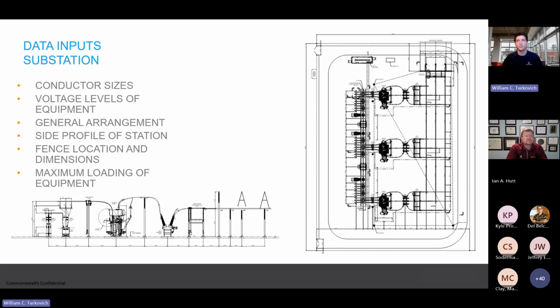We need the general arrangement. On the top right, you can see this example has 3 transformers connected to 3 breakers connected to the collector system and going out to a 3-phase line on the top of the screen. And then you need a side profile to 3-dimensionally describe the characteristics of the substation - how tall the breakers are, where these wires are relative to the ground, and relative to each other. All of these different details factor into how these cables interact with each other through inductive and capacitive coupling.